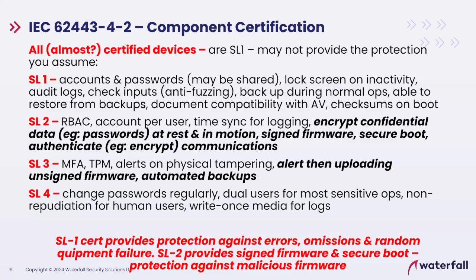It does not say the device has to encrypt its communications, not even when it's sending passwords around. SL2 says you've got to encrypt passwords when you're sending them across the network. SL2 says that you've got to sign your firmware so that you can't send a bunch of zeros. You can't log in with a shared password and no encryption, or steal the password on the network, log in and upload a bunch of zeros as your firmware and turn the device into a brick. It cannot boot anymore, and there's no way to change the firmware anymore. You have to throw the device out and buy a new one.